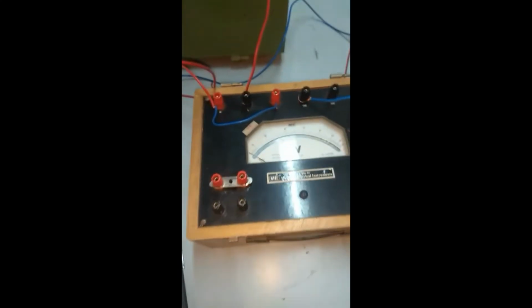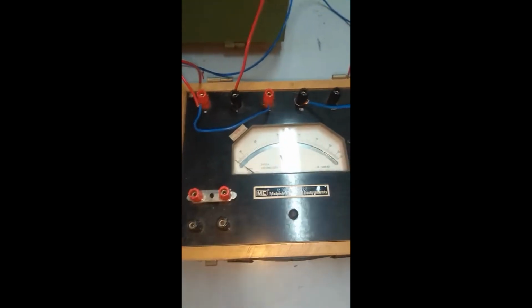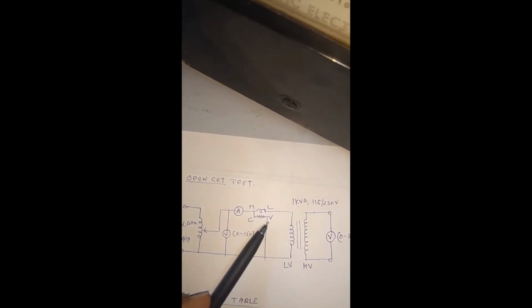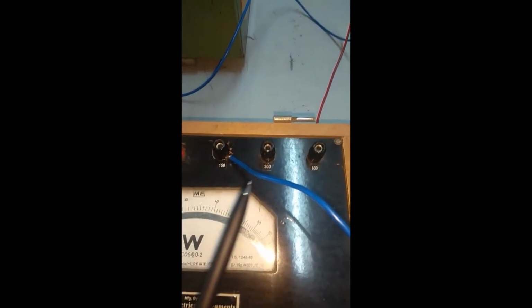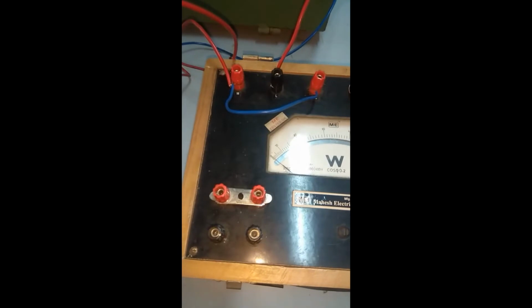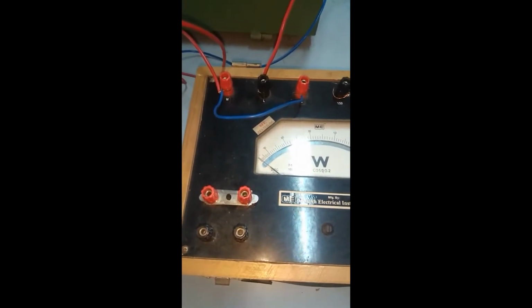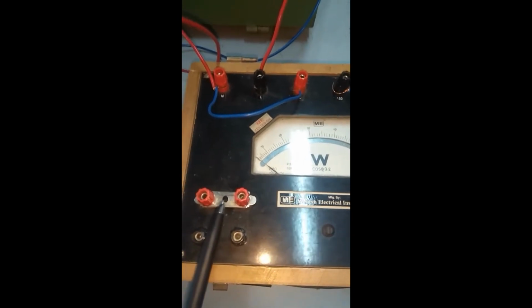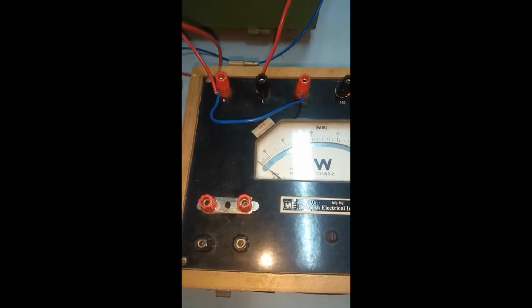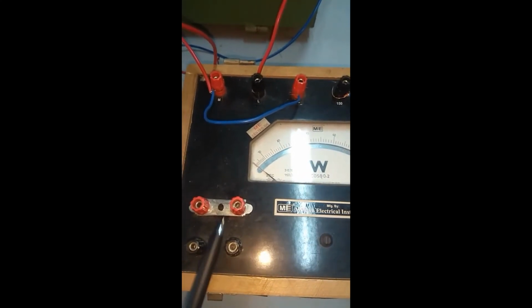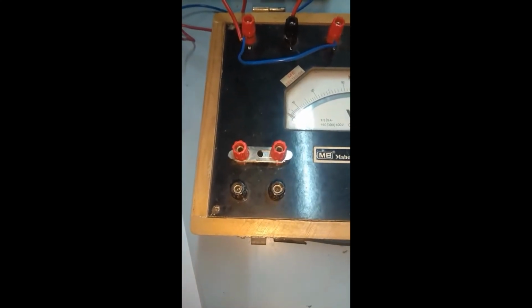And here is the wattmeter. The wattmeter basically has 4 connections, so let's see what those connections are. You can see it has 4 terminals: M is main, L is line, C is common, and V is volt. For V there are 3 ranges: 150 volt, 300 and 600. There are also 2 current ranges. This wattmeter is designed for 2.5 ampere when the connectors are connected this way. When the steel connectors are connected in parallel, we get the higher range, which would be 5 ampere.